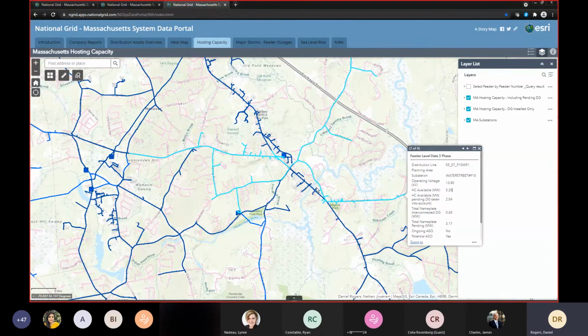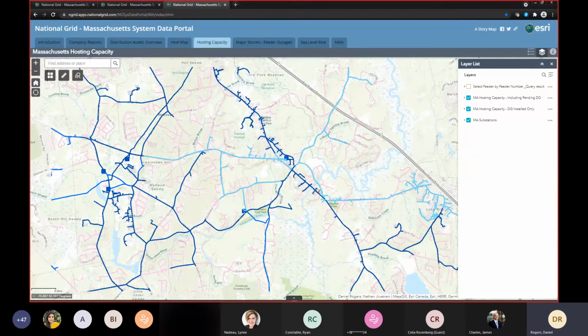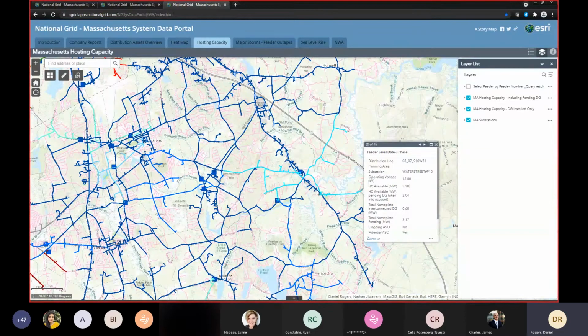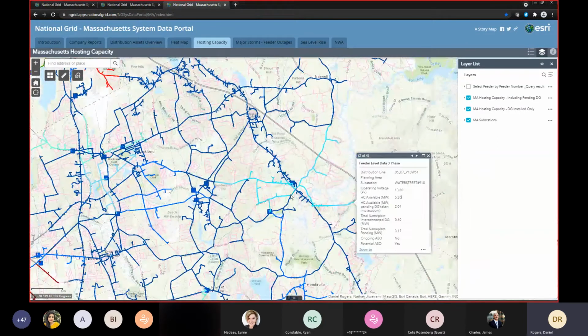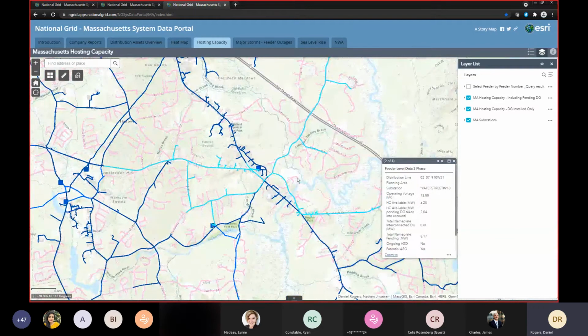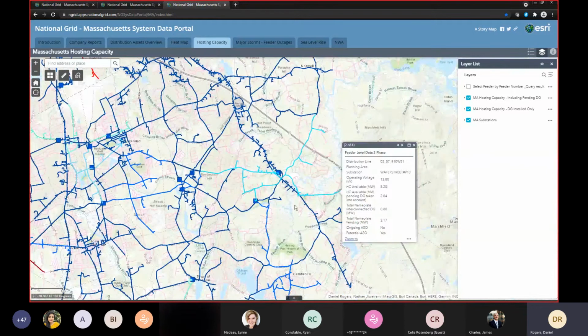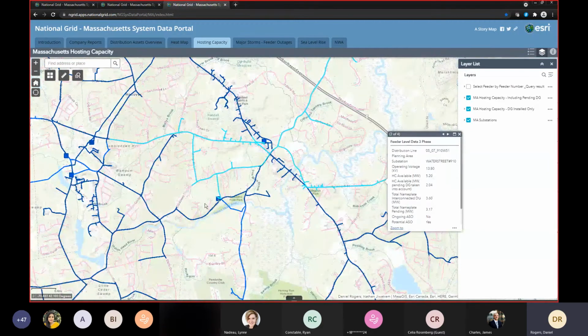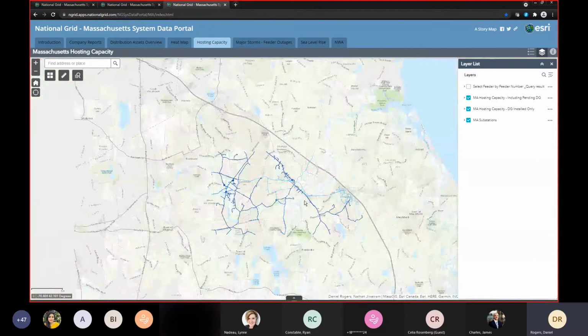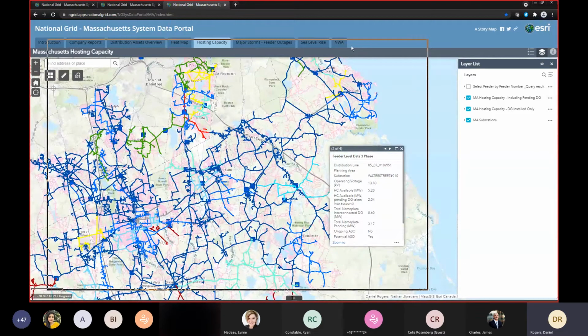And the future update will also increase hosting capacity for certain areas, because with the mass update, we take the newest models from our geographic information system, and that will reflect the increase in your asset improvements from other DG triggered events. So say that this line had interconnected 2 megawatts, and during that they changed regulator settings at the substation and added a recloser that is bidirectional. So now those improvements actually increase the hosting capacity overall. So that is an overview.